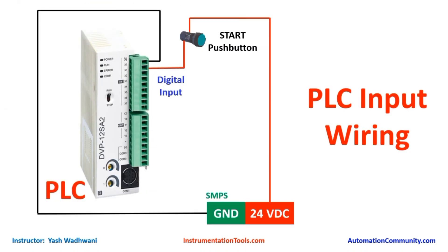Let us understand the wiring requirement for our project. First, let us understand the input circuit. These are our digital inputs in source-sink configuration. First of all, we will connect the ground terminal of our SMPS here. Then 24V DC from the SMPS will be connected to one terminal of our start/stop push button, and its other terminal will connect to the X0 position.